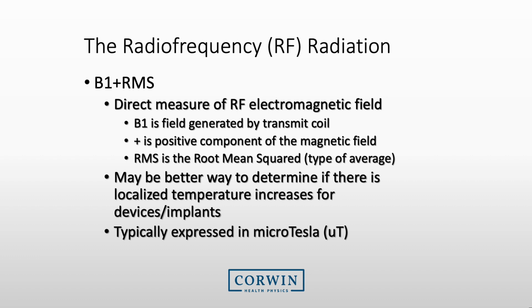Another indicator of RF radiation on newer systems is the B1 plus RMS. This is a direct measure of the RF electromagnetic field and is associated with the magnetic field generated by the transmit coil. This indicator may be a better way to determine if there are any localized temperature increases for devices or implants. It is typically expressed in microtesla.